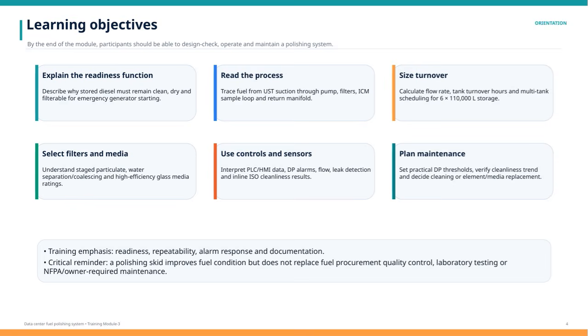You'll learn how to trace the fuel flow from the underground storage tank, through pumps, filters, the ICM sample loop, and back to the return manifold.